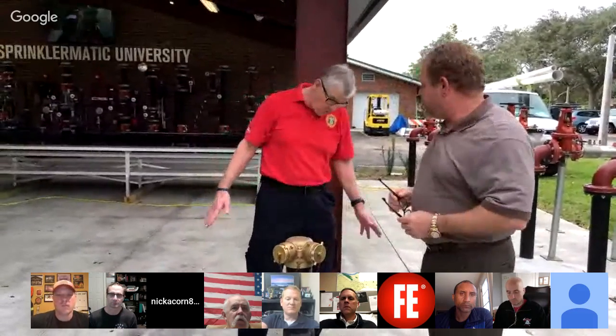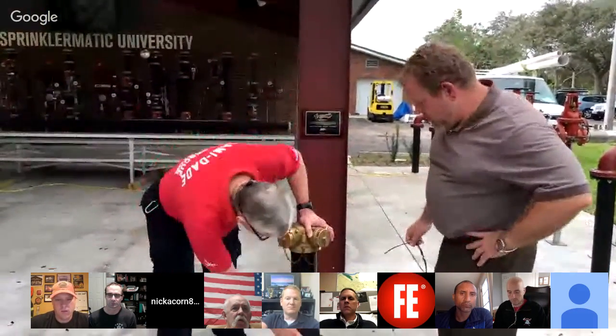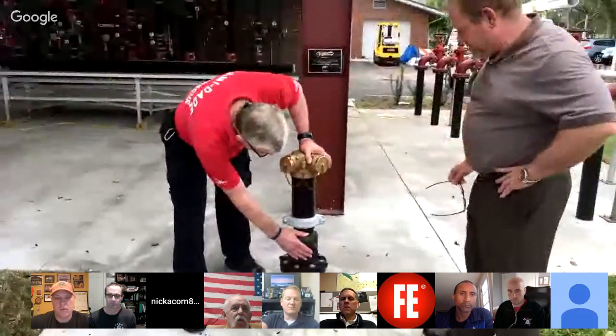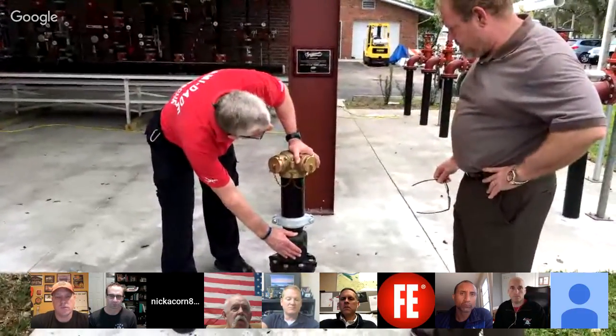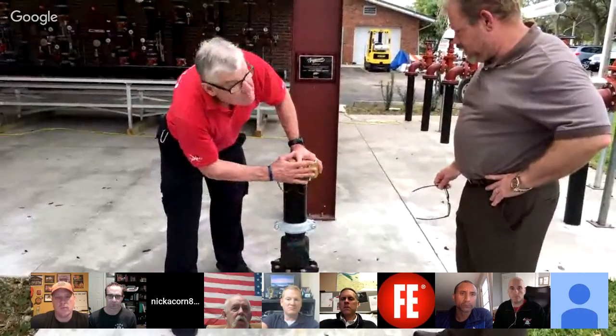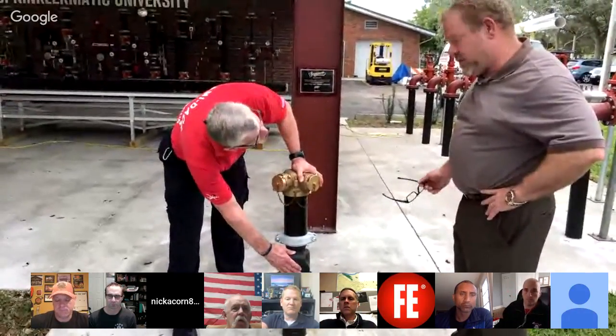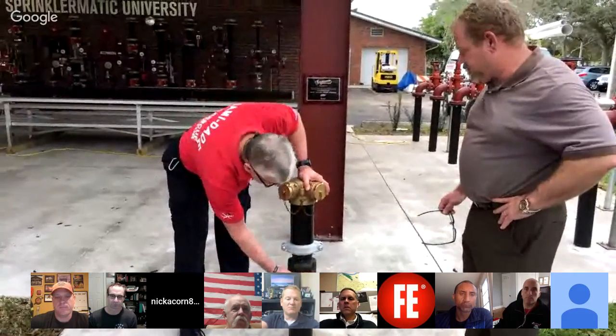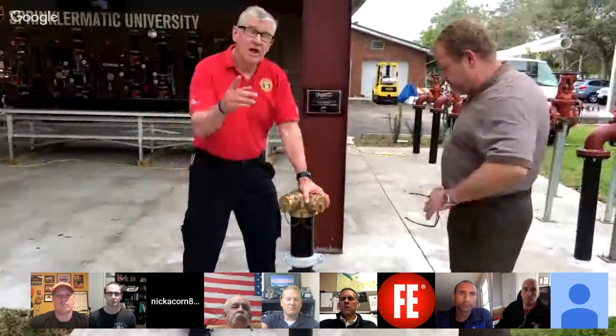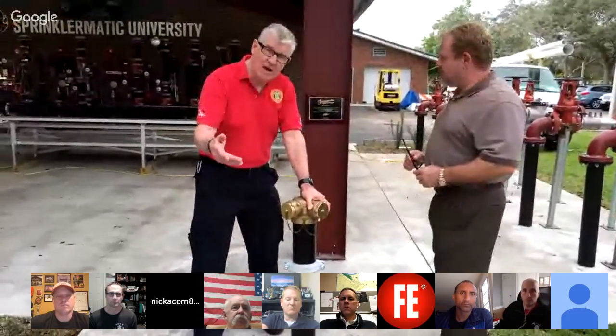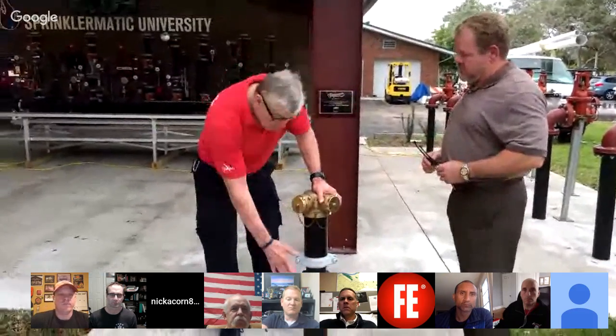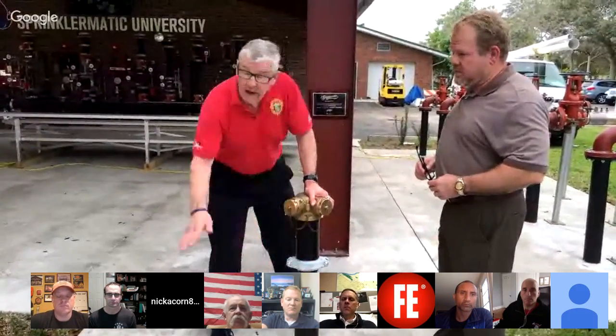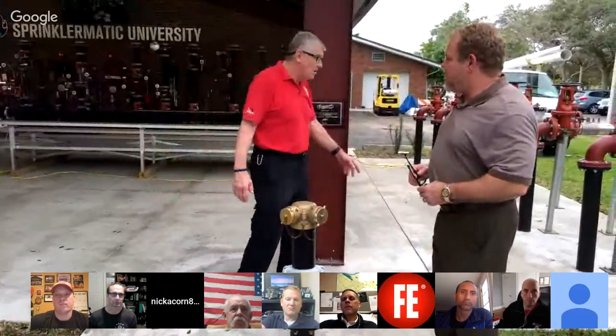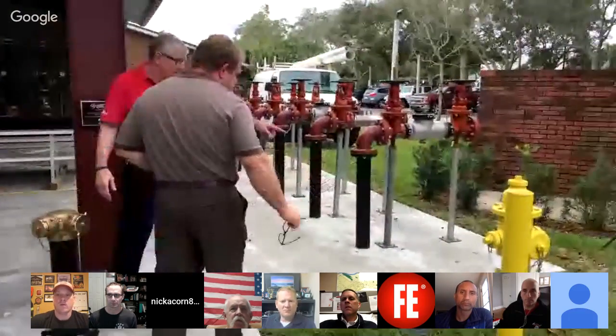Yep. Now, again, this is Florida. This check valve. If the fire pump is pumping 160 psi, and we pump 150 psi, this check valve remains closed because we are pumping up against a closed check valve. Now, when we exceed the pressure developed by the fire pump, we open this check valve, which in colder climates would be inside the building in a heated area, and close the check valve on the discharge side of the fire pump. The fire pump will stop.